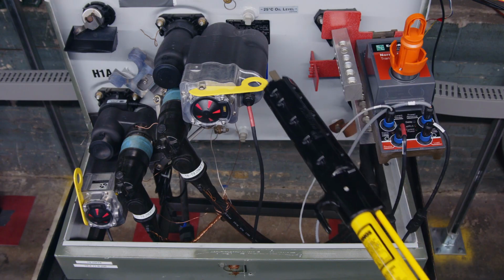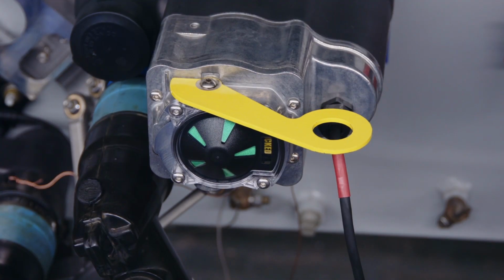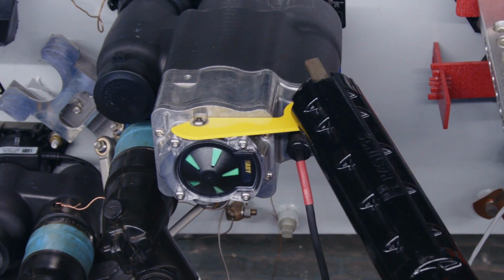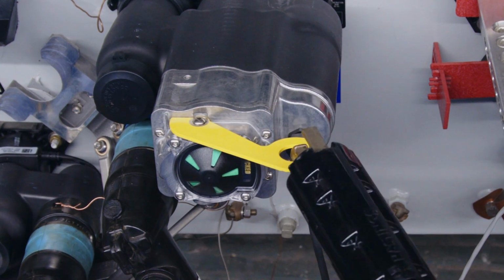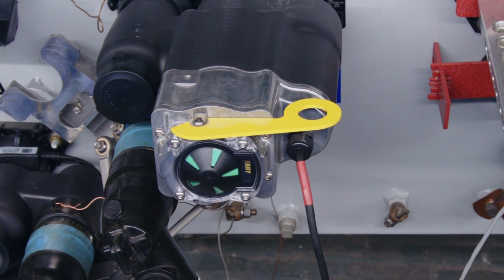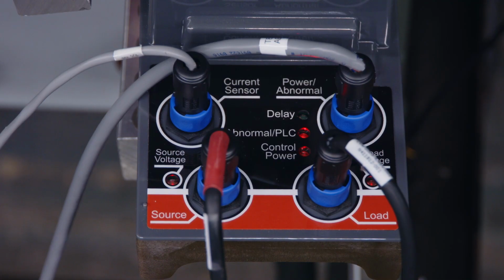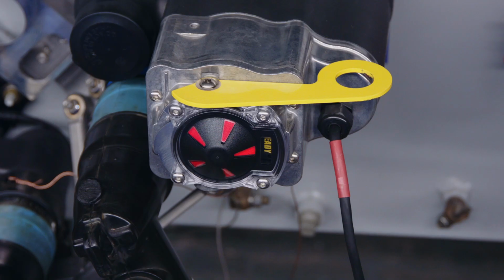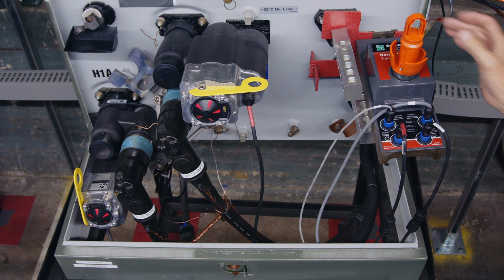Step 10. Open the H1B bushing well interrupter by pulling the yellow lever forward once. Step 11. Close the H1B bushing well interrupter by toggling the handle from the open and locked position to the ready position 3 times, ending in the ready position. Step 12. Make sure the delay LED is blinking. It will blink 10 times and then the bushing well interrupter will close. Step 13. Make sure the indicator on the bushing well interrupter is in the closed and ready position. Step 14. Remove the cordless power module.